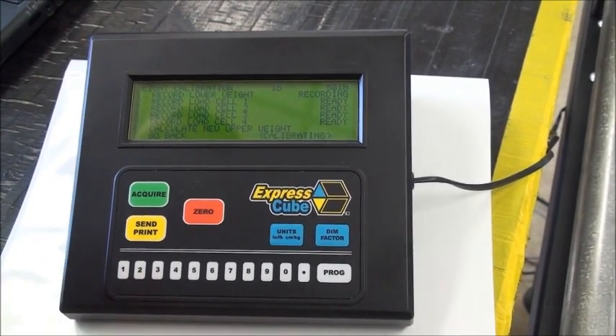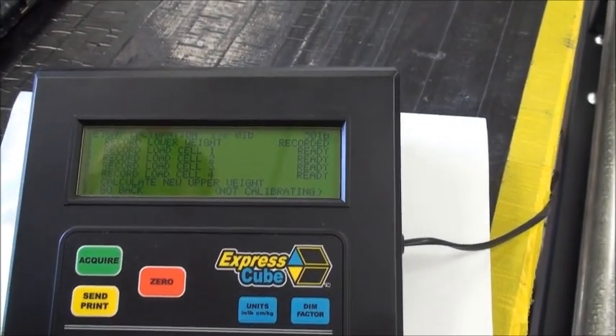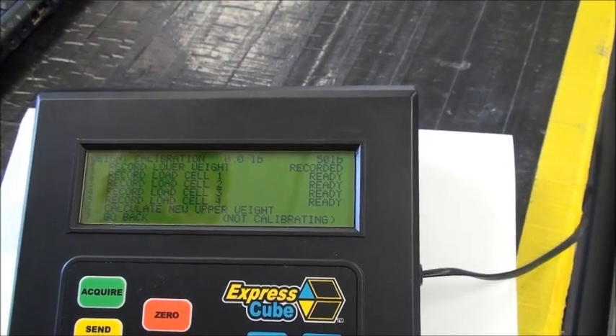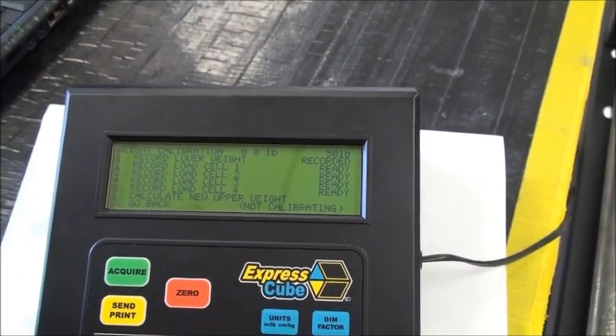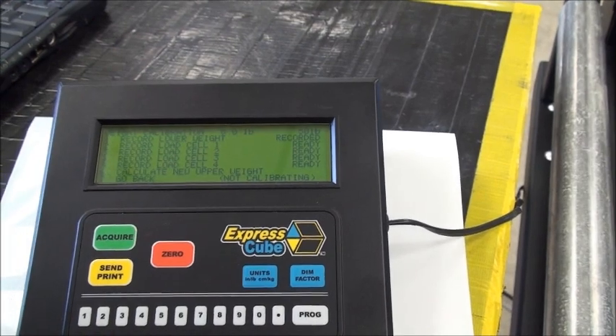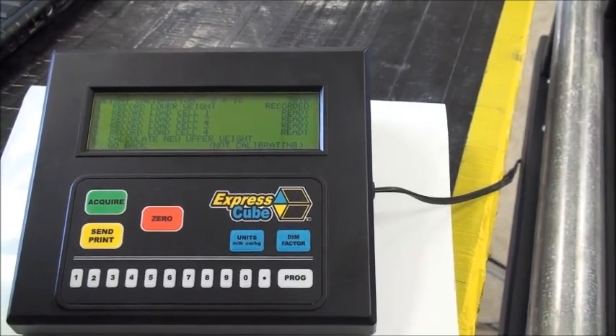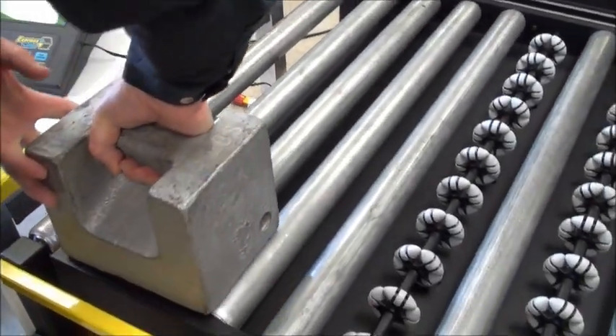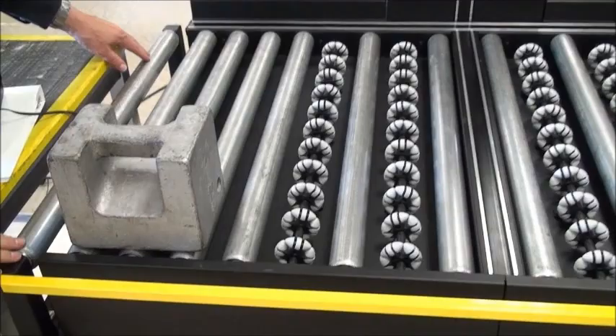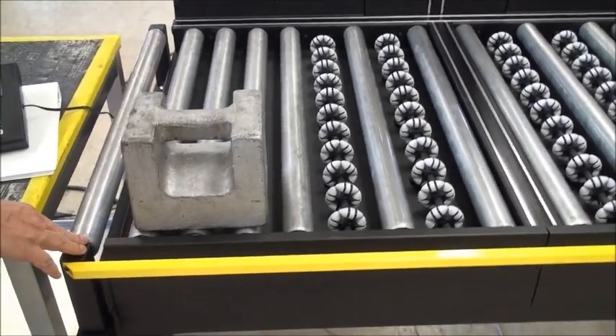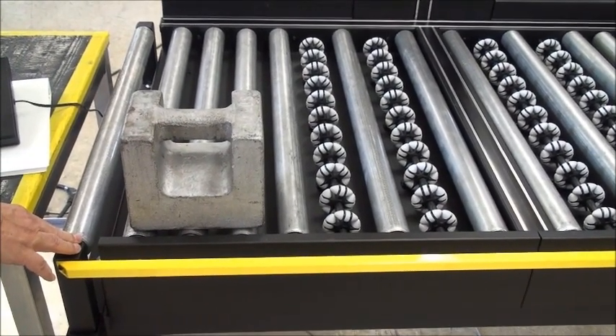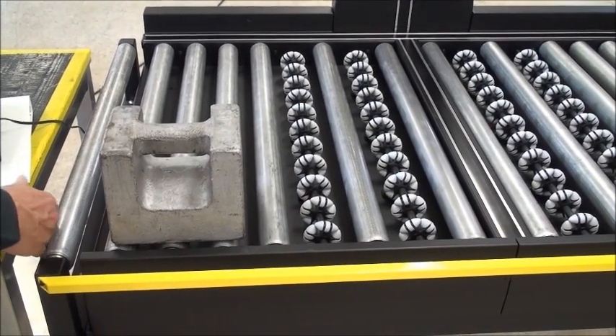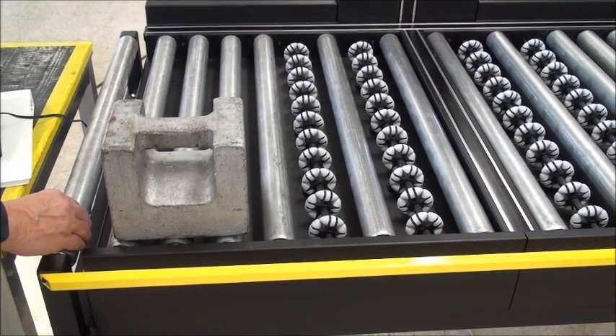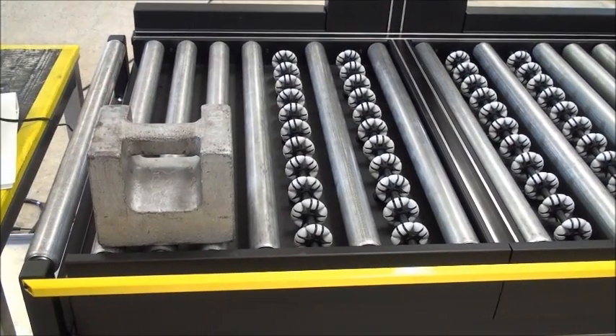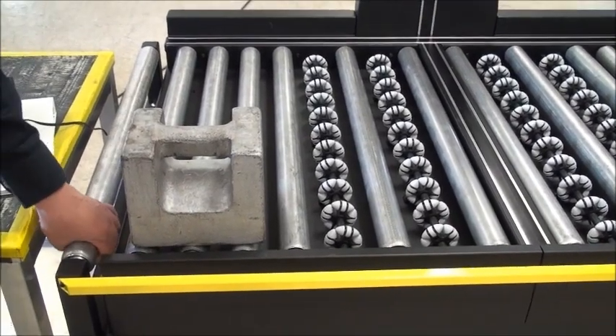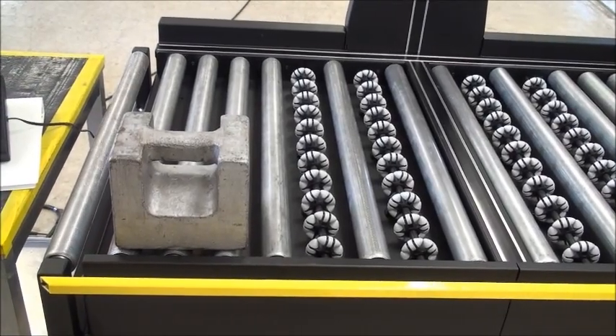I need to record that. If I press the button here, you'll see recording. It's recorded. All right. Now I've got to record load cell number 1. It doesn't matter really which load cell you do first, but there's 1 in each corner. I can start in any corner. I'm going to mention one thing for you to be careful of. This last roller is a fixed roller. It is used when they do the initial setup of the machines. The idea is that it helps protect the scale from excessive banging, because this roller is usually set slightly higher so that the box hits here and it drops on the platform. But it is not part of the platform. In other words, this does not actually add to the weight.